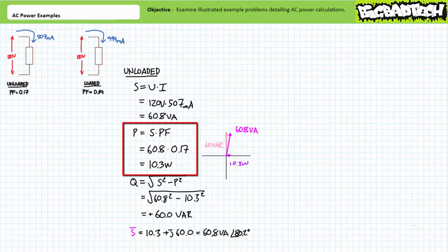Real power is apparent power magnitude times power factor. In the unloaded condition, an extremely lame 0.17. Substituting in our given values yields a real power consumption of only 10.3 watts. This is the small amount of real power accounting for frictional heat losses when the unopposed motor is just free spinning and not doing any actual work. As we anticipated, real power in the unloaded condition is relatively small, meaning only a small portion of power the motor is apparently consuming is being directed towards actual work, and a vast majority of it will be directed towards a reactive interchange characteristic of primarily inductive elements like motor windings.